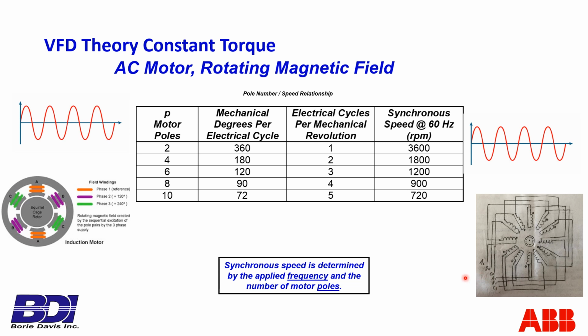If you look closely, there's a phase A, and it comes in, goes through that winding, comes out, goes to another winding, and goes out at now I'm at 180 degrees going through another winding, and then over here to 270 degrees, there's another winding, and then I come out the A naught phase right there, the other end of the winding connection. So this is a four-pole motor because there's four poles in the stator per phase.